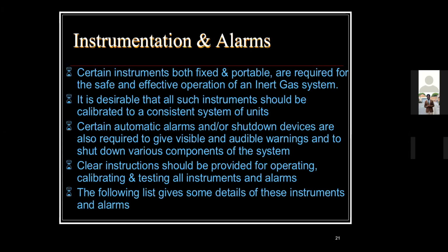If you also look at the incident of the Piper Alpha disaster, the first indication of alarm, one of the pressure pumps was put out of service, but there was no tag and a lot of things. Even though most of these accidents are attributed to safety culture and failure in management system, you can still see that you can't overlook certain alarms.